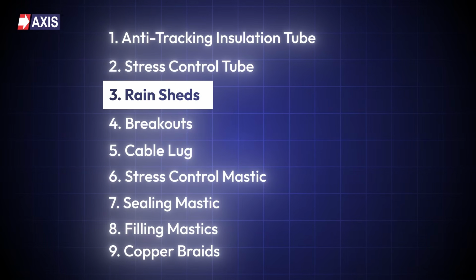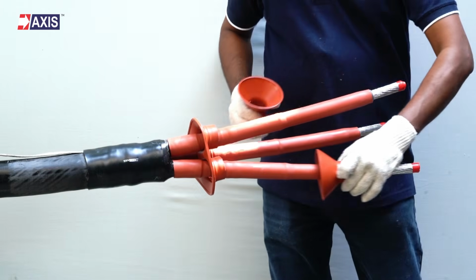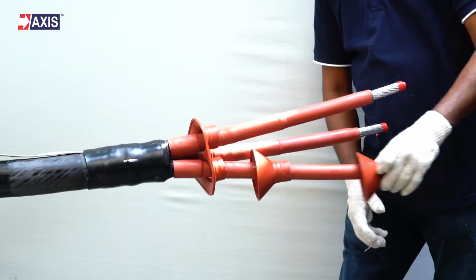Thirdly, rain sheds. These are used to increase creepage distance and control surface leakage currents. For 11 kV terminations, rain sheds are used only in outdoor installations. For higher voltage terminations, rain sheds are used in both indoor and outdoor applications to improve insulation performance and reduce the risk of cracking and flashover.